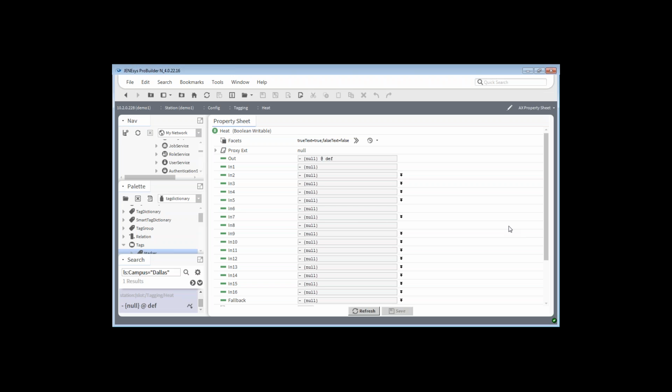But for a single building application, that doesn't seem as powerful with the tagging by itself. But once you've actually looked at doing it based on establishing templates or using templates or finding a problem quickly: if I need to look at every VAV in the building quickly, I could still go through the old BQL method, but if they're in this search, I can look for the VAVs and do a search on the related AHUs or rooftop units that are associated all the way up the chain.